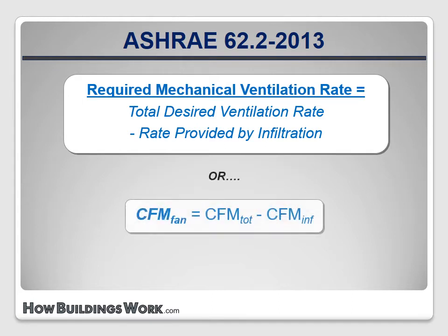We'll call the fan rate CFM fan, we'll call the total desired ventilation rate CFM total, and we'll call the infiltration rate CFM infiltration. That's close to the nomenclature used in the standard. So the overall equation is: CFM fan equals CFM total minus CFM infiltration.